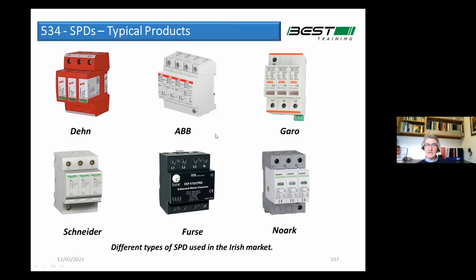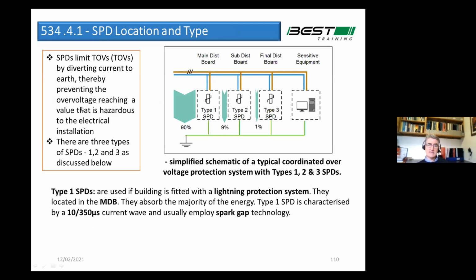So that's what they look like. And there are types 1, 2, and 3, as you probably know. Type 1 is used on all buildings where you have lightning protection, or where there's a risk of a direct lightning strike. For example, if you had overhead cables bracketed straight onto the wall of your premises and then a cable coming down, that would be a direct risk as well. If you have lightning conductors on your building, that's a direct risk, because the lightning strikes, hits the ground, goes back up through your earthing system, and tries to spread its way through your installation and burn everything in its pathway.